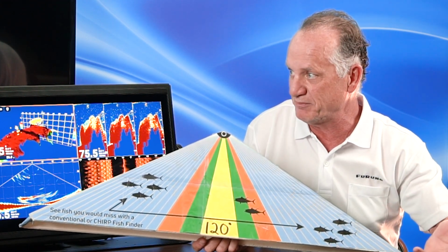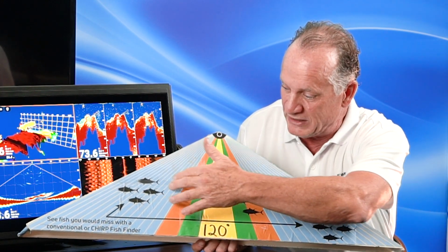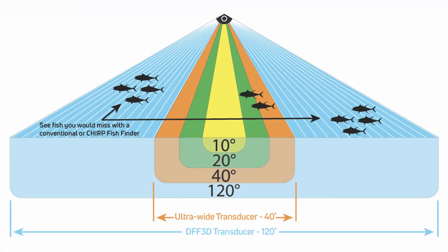Yeah, let's look at the real key to the DFF3D technology, and that is the actual beam pattern and the way we break up the beam. So let's look at the difference between the DFF3D beam pattern and a normal single element transducer beam pattern. With the DFF3D, we have multiple elements which we can phase. In other words, we can time when each element fires and create a steered beam pattern. That's the key technology of the DFF3D, and it was so revolutionary at the time, and why we've won so many awards with it, because it allows us to create this full 120-degree sweep, and we can break that 120 degrees into 40 individual 3-degree channels, for example.